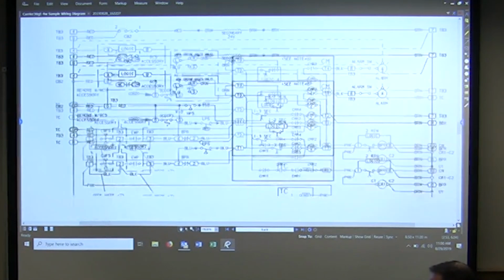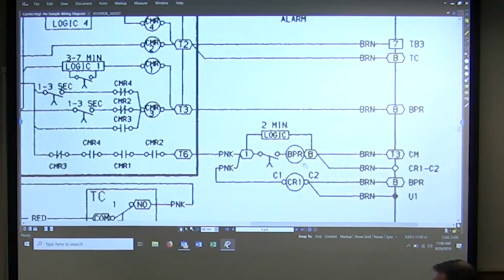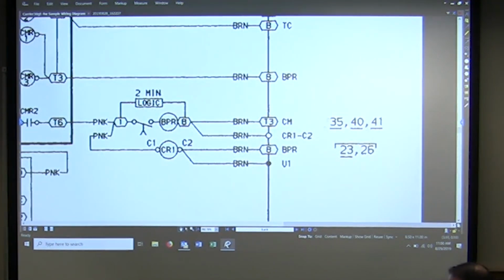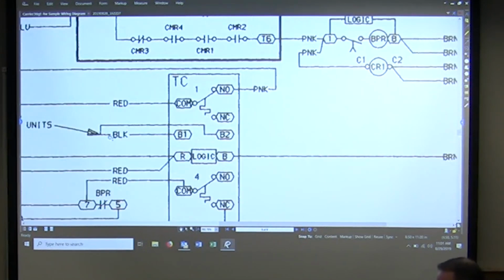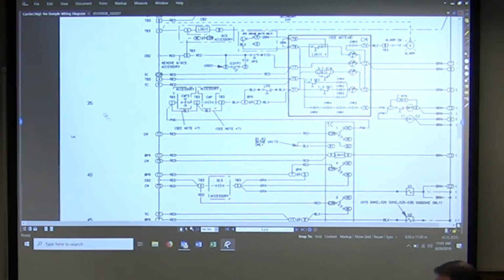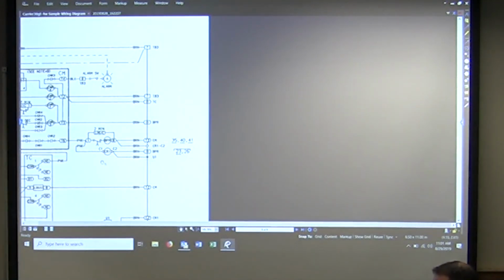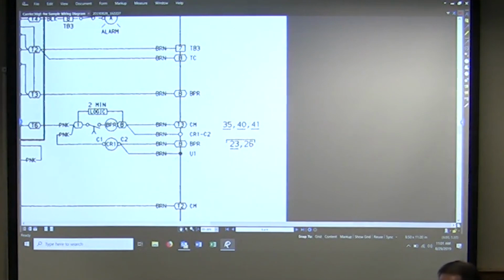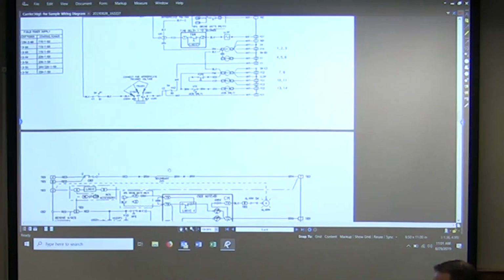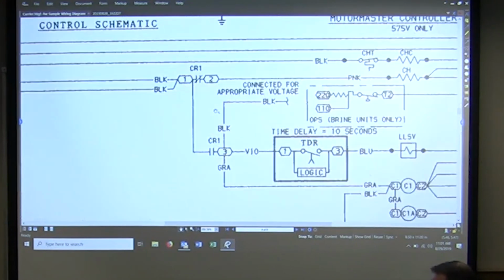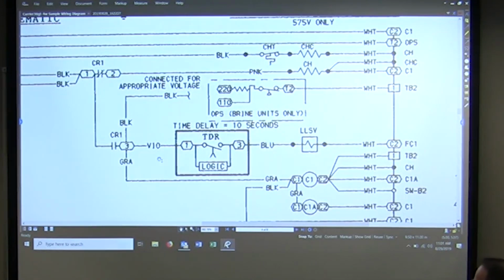And then the last one: what is the purpose of CR1? Where is CR1? To the right. So CR1's here. Now, one thing I didn't point out to you: these numbers over here on the side indicate what line the corresponding contacts may be found. So BPR, for instance, since we're right here at 35, see here's 35, there's BPR right there, and at 40 there's another BPR. So if we're looking at CR1, it's saying lines 23, 26. If I come up here to 23, 26, there's my CR1 contacts. So what are those doing?